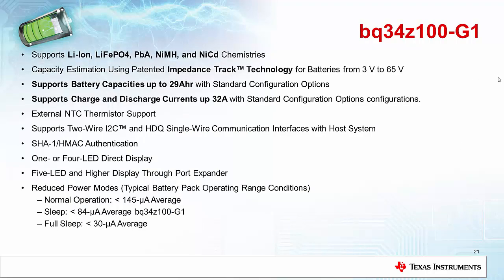The 34Z100G1 is a gauge-only device with algorithm support for lithium-ion, iron phosphate, as well as lead-acid, nickel metal hydride, and NiCad batteries. This is using our impedance track technology. Natively supports up to 65 volts, and then can be, as I mentioned earlier, scaled for even higher voltages. Capacities up to 29 amp hours, currents up to 32 amps, which can both be scaled for higher voltage systems. Supports 2-wire I2C as well as the HDQ single-wire communication. We can support up to 4 LEDs directly on the part, and also have support for a port expander for an even higher number of LEDs. And SHA-1 HMAC authentication support.